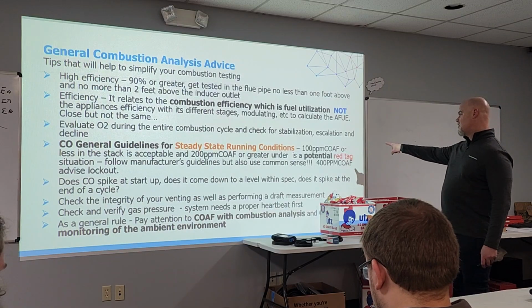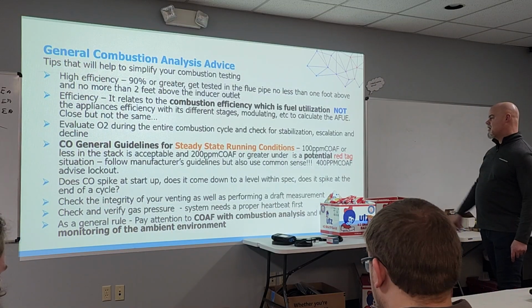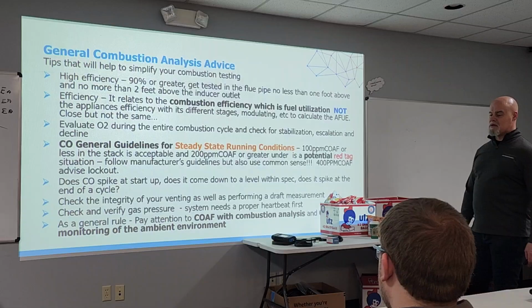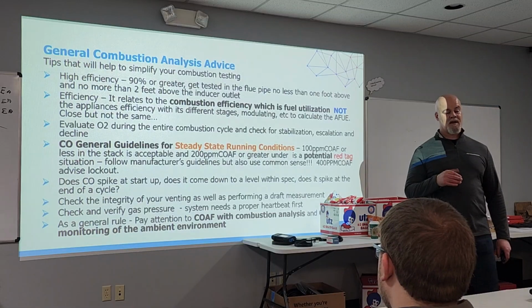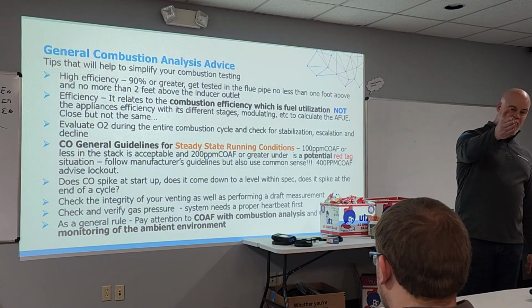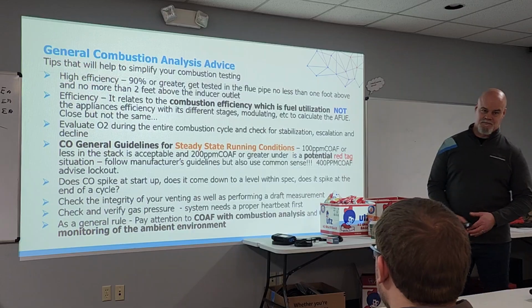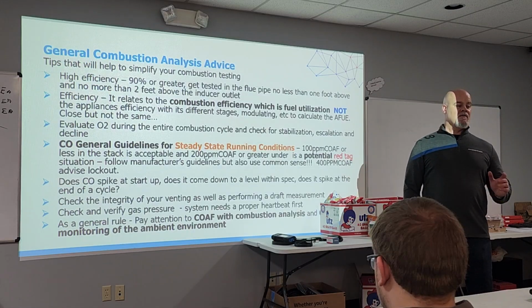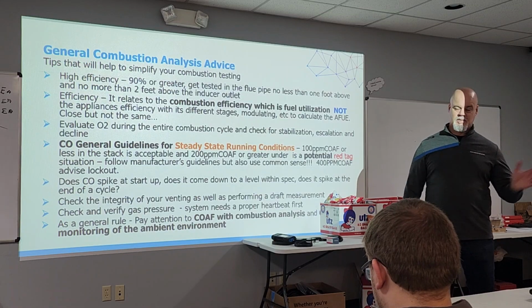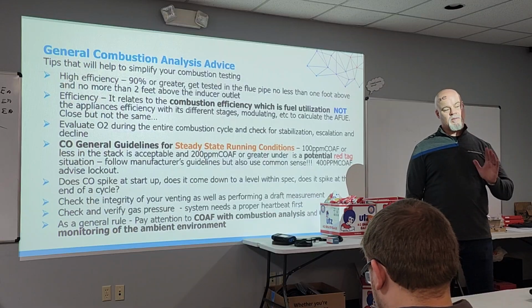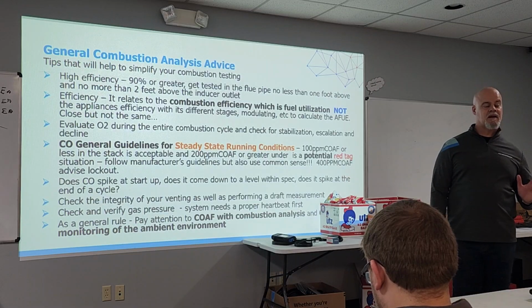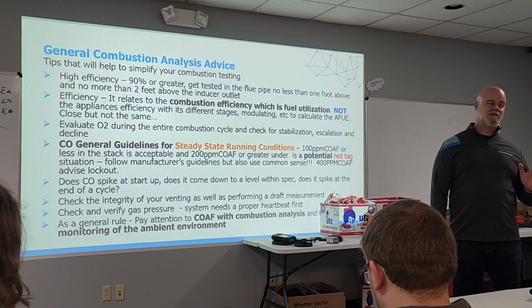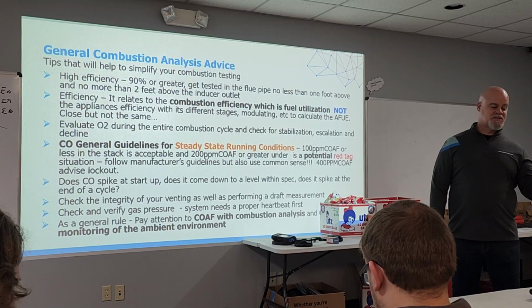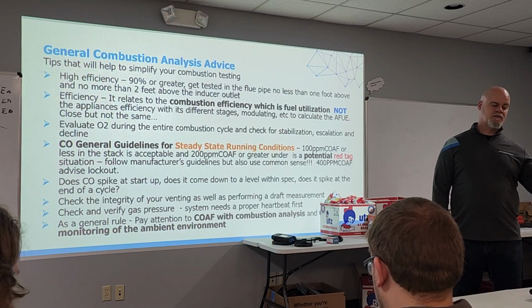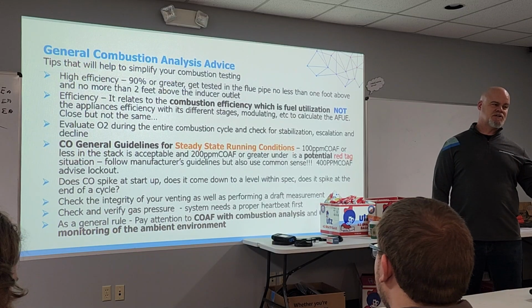Very important. And then 400 ppm or greater is an advice to lock out, which means the system should be shut down. Now, do you guys have a red tag protocol here? Yeah. Perfect. If anybody in here has worked for different companies, which I'm sure you have, please make sure if you're combustion testing or anything like that, that you have a red tag protocol. What the red tag protocol tells you is what to say, how to act, and what to do when you have to potentially shut a system down.